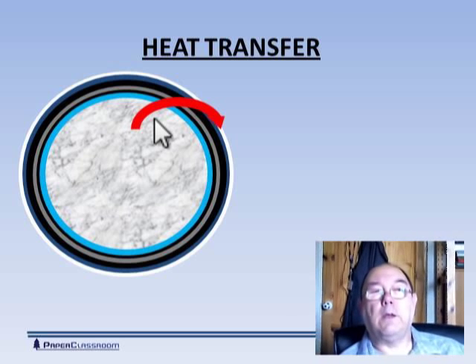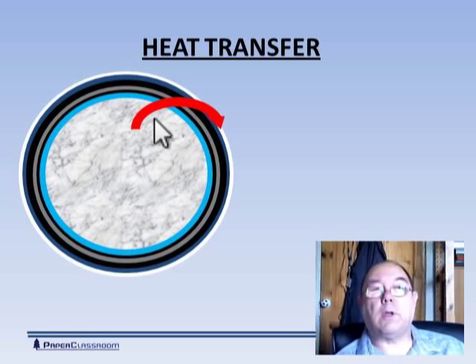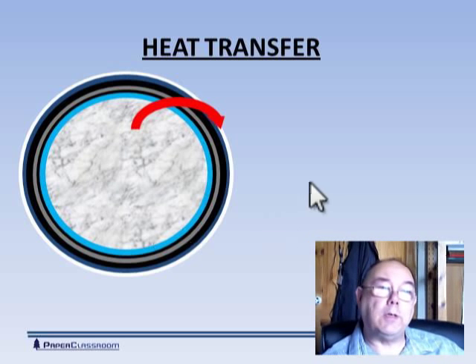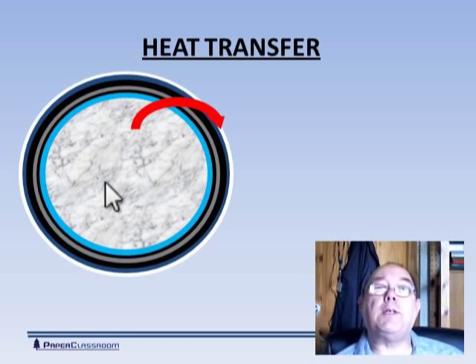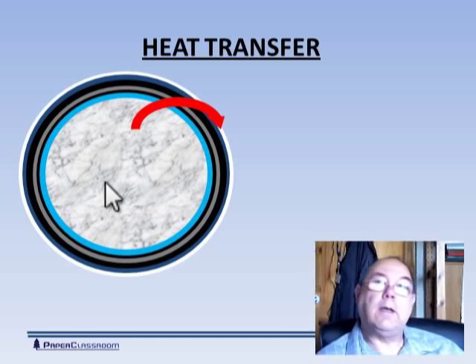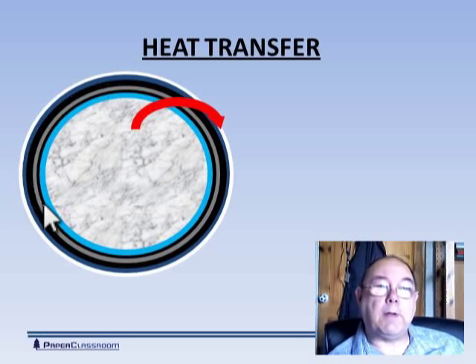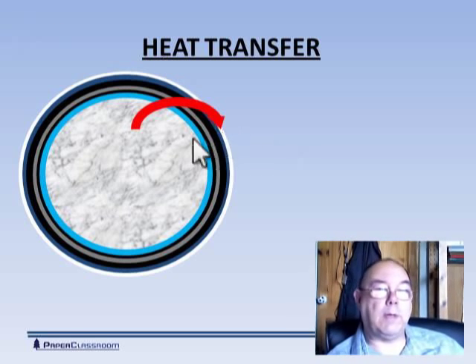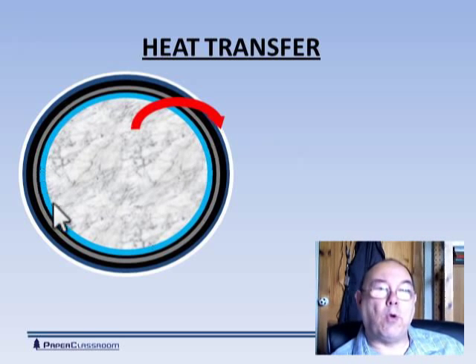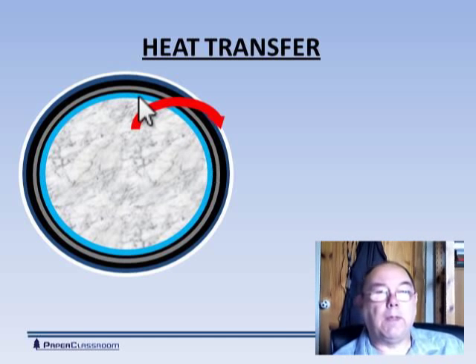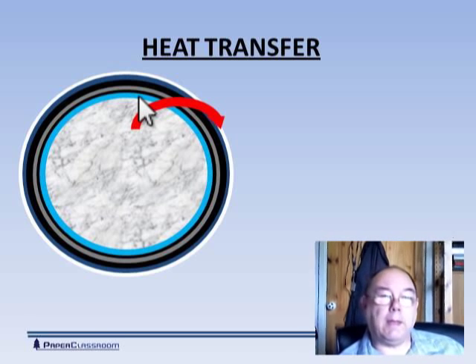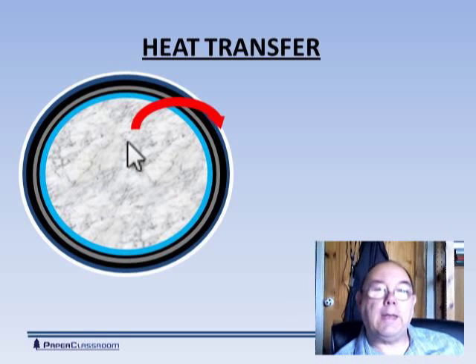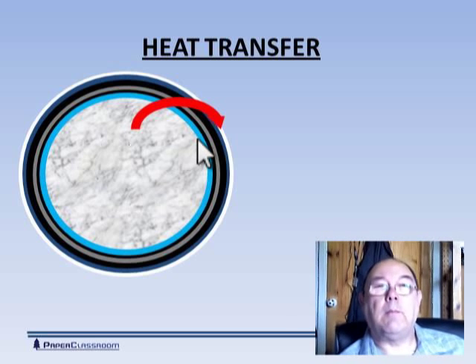That heat will eventually dry the paper, but on its path there are restrictions, as illustrated here. Imagine this cylinder is filled full of steam. The steam condenses and forms water, and with a typical drying cylinder, if the sheet is being made at over about 300 meters a minute, the condensed water will be thrown against the internal edge of the drying cylinder in what we call rimming. Here it forms a layer that's quite a good insulator, so not all the heat from the steam will be able to get through this layer of water because of its insulating properties.